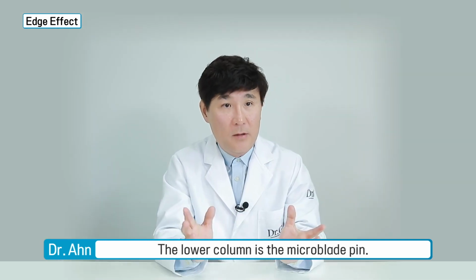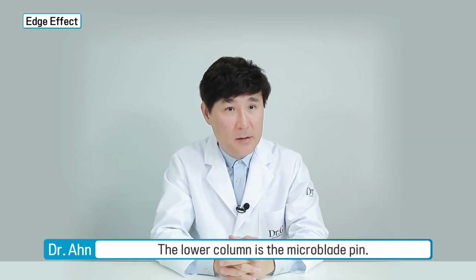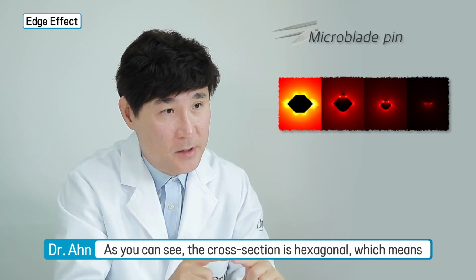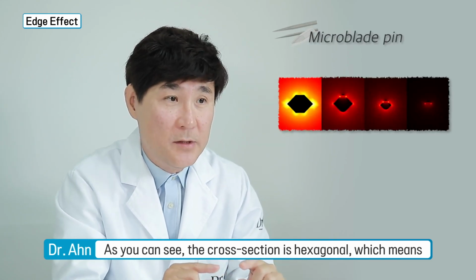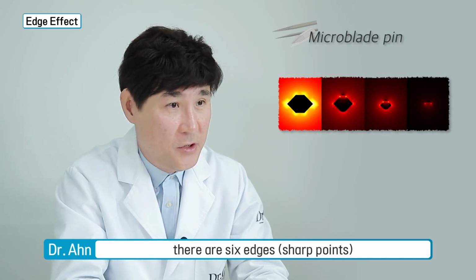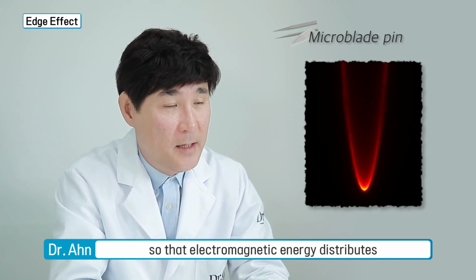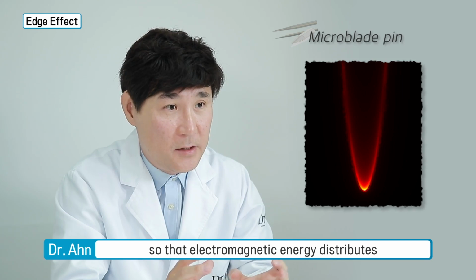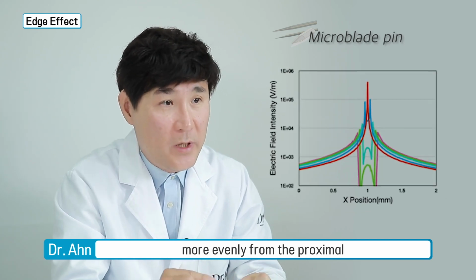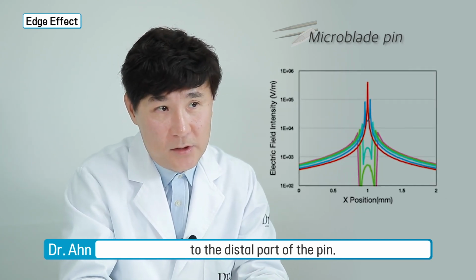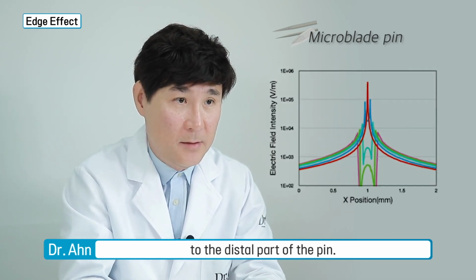The lower column is the microblade pin. As you can see, the cross section is hexagonal, which means there are 6 edges, sharp points, so that electromagnetic energy distributes more evenly from the proximal to the distal part of the pin.